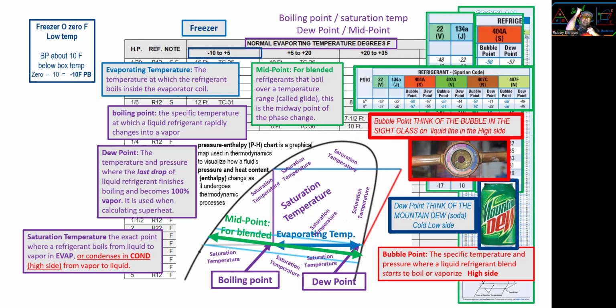The high temperature moves to cold temperature, right? So we need the evaporator colder than the room temperature for heat to go in. Now, that's for the freezer. Low temp. So the evaporator temperature should be at least 0 to -10 boiling point, because the freezer temperature is around 0 degrees, and we need to go in it. So it's got to be a colder boiling temperature. So for freezers, the boiling temperature is -10.